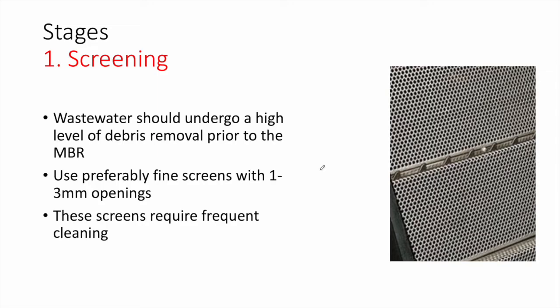Now we will study each stage individually. First, the screening. The wastewater should undergo a high level of debris removal prior to the MBR; otherwise you will face fouling of the membrane, clogging, and serious costly problems. Use preferably fine screens with one to three millimeter openings. As you can see here, the openings are very tiny, but this will require frequent cleaning.